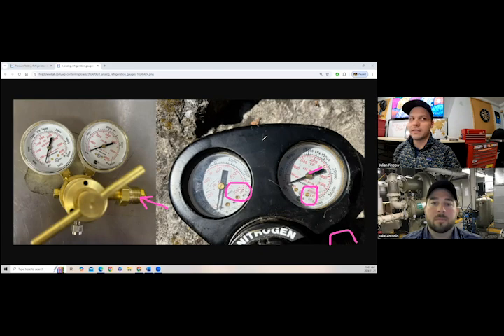And I think what is maybe misleading about that is it makes you feel like you can get 1,000 psi out of that regulator. You're like, okay, the regulator says it'll let me put 1,000 psi out. I should be able to pressure test stuff to 1,000 psi. But because of pressure differential and volume of the bottle versus the system you're testing, in practical experience, Jake and I were just agreeing, you're not really going to get more than like 440, 450 psig out of a standard bottle with this regulator, right?